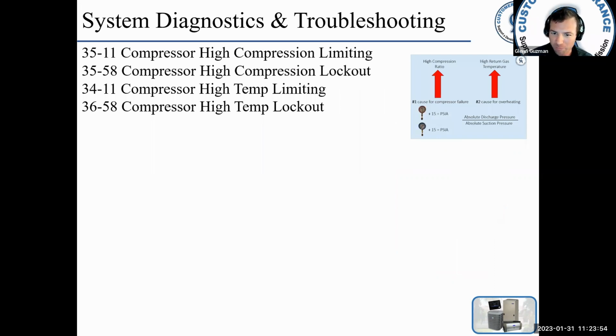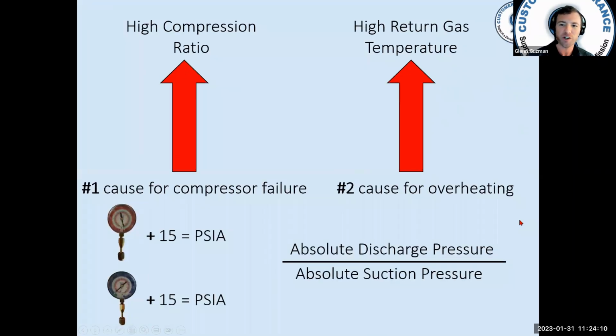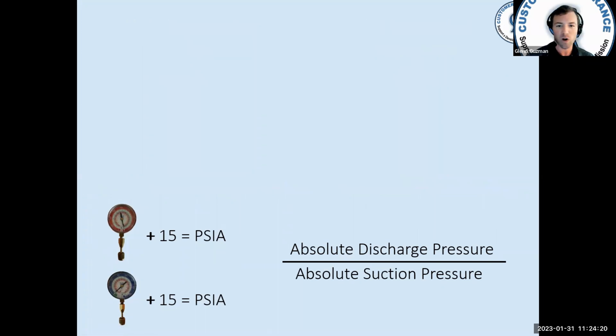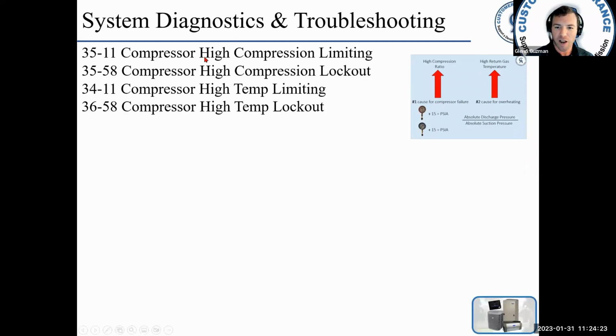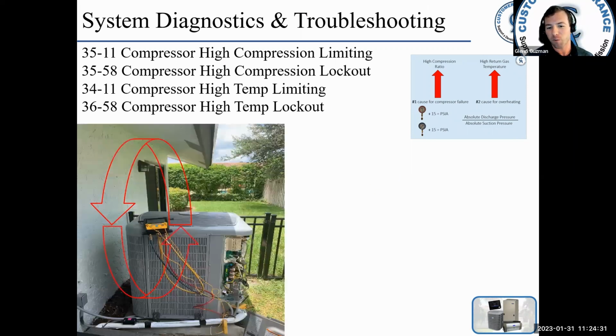3511, high compression limiting. 3558, compressor high compression lockout. And then 3411, high temp limiting. 3658, high temp lockout. Okay. Looking here, high compression ratio and high return gas temperature are the number one and number two causes for compressor failure. And so that is what this is telling you. High compression and high temperature limiting, it's limiting the operation of the equipment. Okay, that's the number one and number two failure.